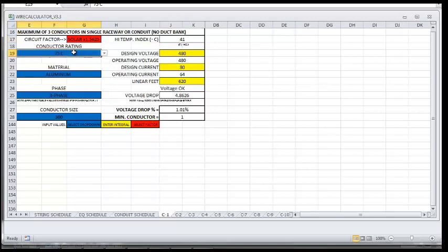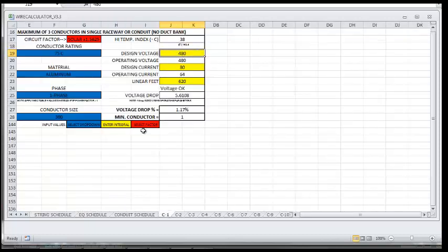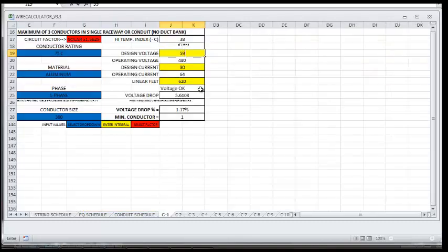So we're there. So we're looking at our D rate. Okay, conductor rating. Let's leave that 75C. Material. Let's leave that aluminum for the conductor. This is single phase, since our first conductors that we're going to be calculating are DC. The temperature, let's pull that from the temperatures back here. So that's 38 degrees Celsius, and below that it does a little calculation showing you what it is in Fahrenheit as well. Okay, so let's get into our inputs.